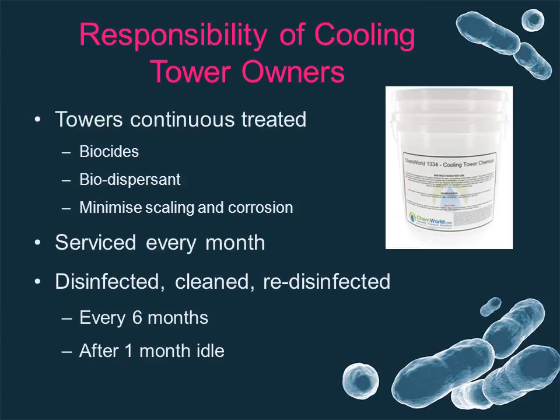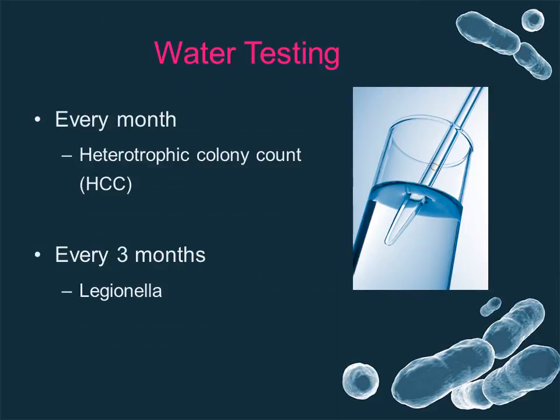The Public Health and Wellbeing Regulations 2009 sets out several responsibilities of cooling tower owners or operators. It states that cooling towers must be continuously treated with appropriate biocides, biodispersants, as well as chemicals to minimize scaling and corrosion. It also states that cooling towers must be serviced every month and that they must be disinfected, cleaned, and re-disinfected every 6 months or after the tower has been idle. It also states that cooling tower water must be tested every month for heterotrophic colony count, or HCC, and tested every 3 months for Legionella.